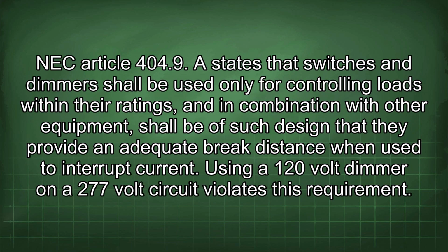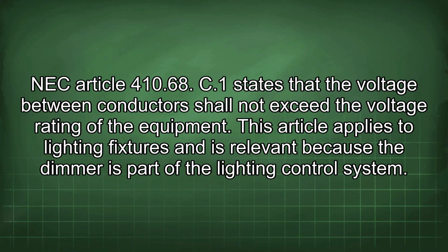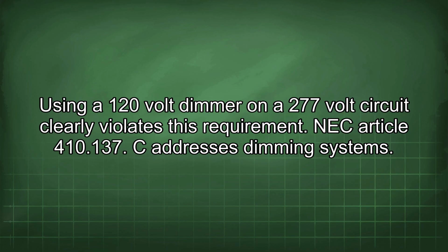NEC Article 404.9 states that switches and dimmers shall be used only for controlling loads within their ratings, and in combination with other equipment, shall be of such design that they provide an adequate break distance when used to interrupt current. Using a 120-volt dimmer on a 277-volt circuit violates this requirement. NEC Article 410.68(C)(1) states that the voltage between conductors shall not exceed the voltage rating of the equipment. This article applies to lighting fixtures and is relevant because the dimmer is part of the lighting control system. Using a 120-volt dimmer on a 277-volt circuit clearly violates this requirement.